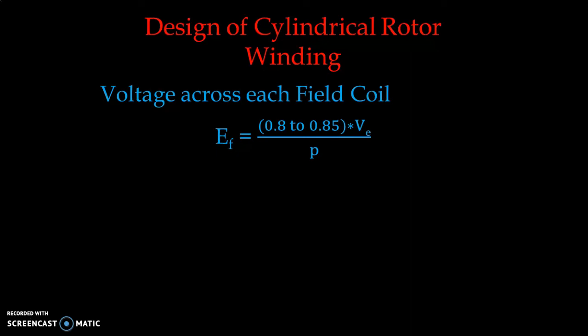The excitation voltage is normally known or fixed by the customer, typically around 125 volts but can vary based on requirements. 15 to 20 percent of the excitation voltage is consumed by the field rheostat or starters, and 80 to 85 percent reaches the field coil. Therefore, the voltage across each field coil is Ef = (0.8 to 0.85) × Ve / P, and this can be easily calculated.